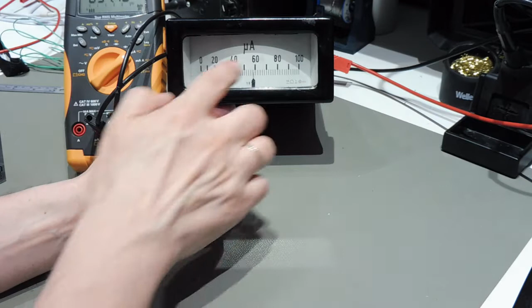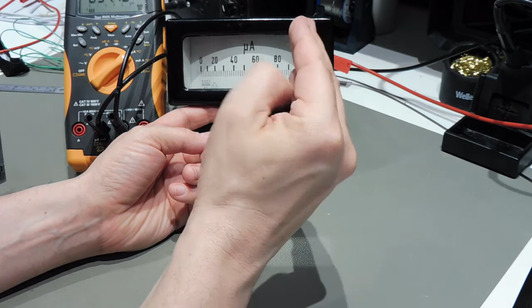They are also easier to read, because with the scale you really need to make sure you look exactly perpendicular to it, otherwise you might get a parallax error where you read the value from a slight angle and read it differently - at least as long as you want a very precise reading. More expensive analog meters even have a mirror on their scale, so you can exactly check that you are looking at it at the correct angle.